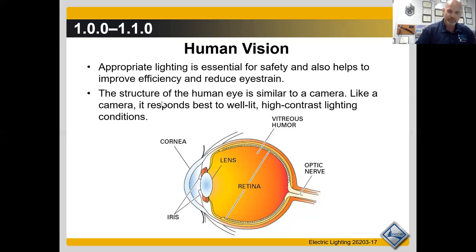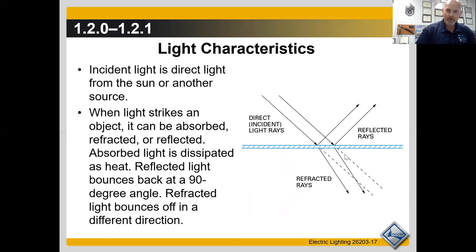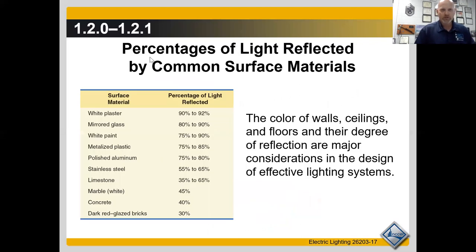Looking at figure three: direct incident light rays. If it's reflected, it bounces off. If it's absorbed, it goes straight in. If it's refracted, it partially bends through. Table one shows percentages of light reflected by common surfaces. The color of walls, ceilings, and floors, and their degree of reflection are major considerations in the design of effective lighting systems. White plaster reflects 90 to 92 percent.